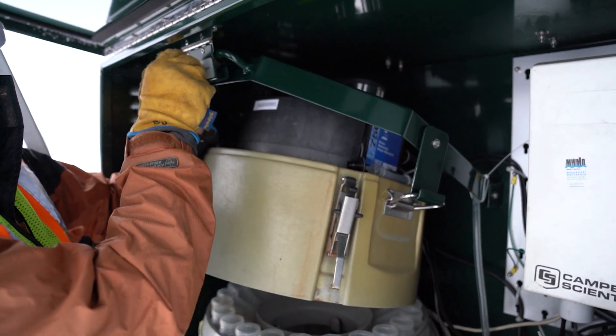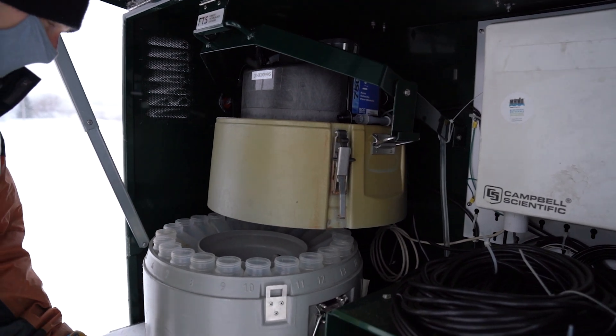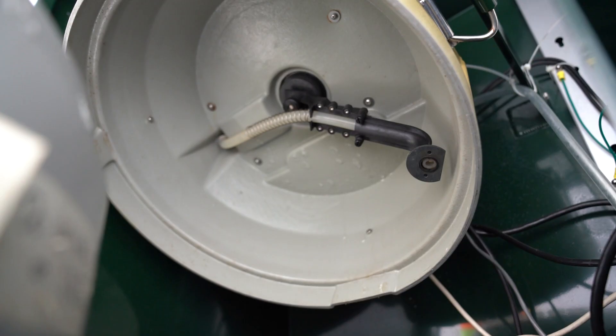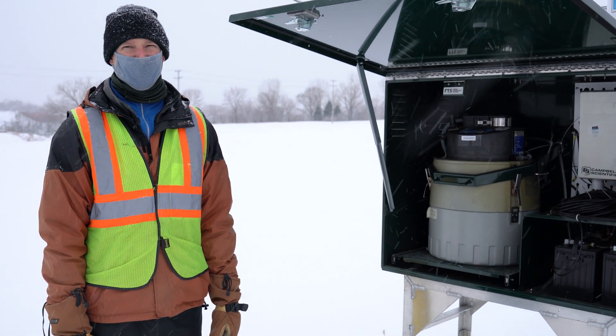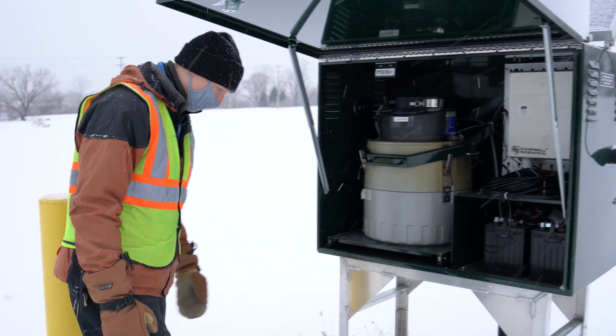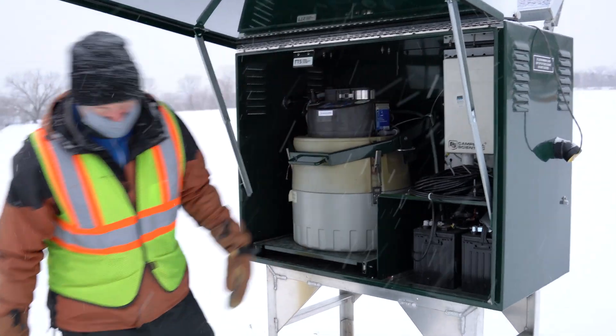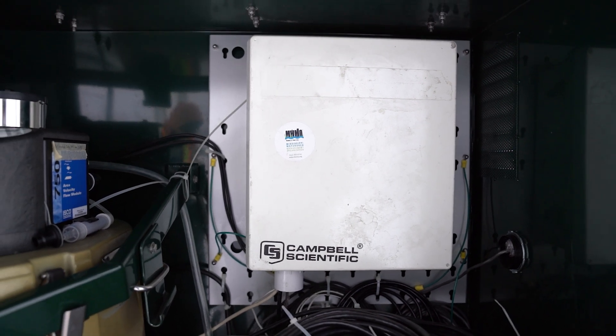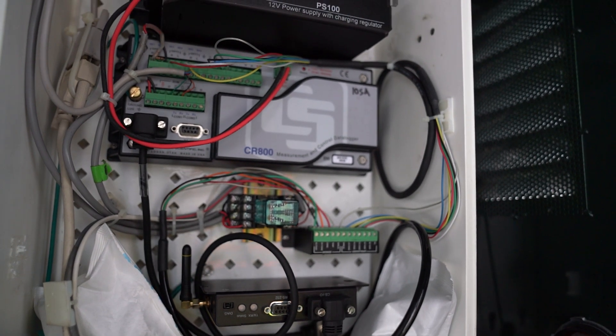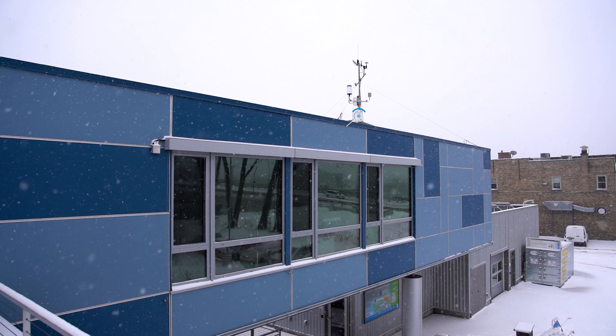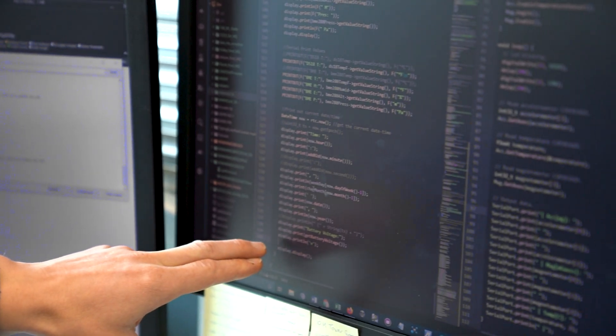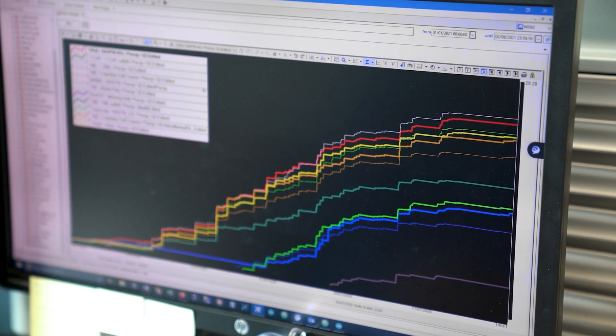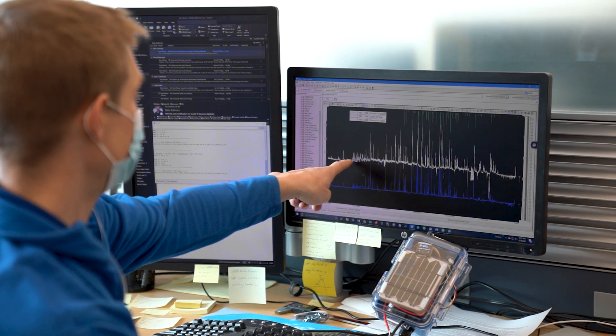We can collect automated flow-paced samples with this equipment, which means that we can calculate the total load of pollution going to the river by collecting the water quantity and the water quality data. On the right, we've got a data logger with telemetry so that as we collect the data, we can see the data on our computers in the office as it's coming in through radios. This system collects the data, logs the data, sends it to our server, and then our server ingests the data so that we can look at it in context — see graphs from a day, a month, a year.